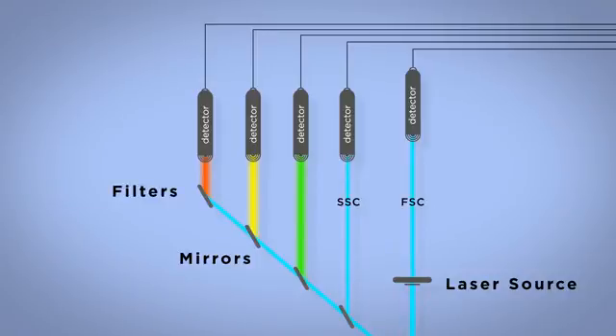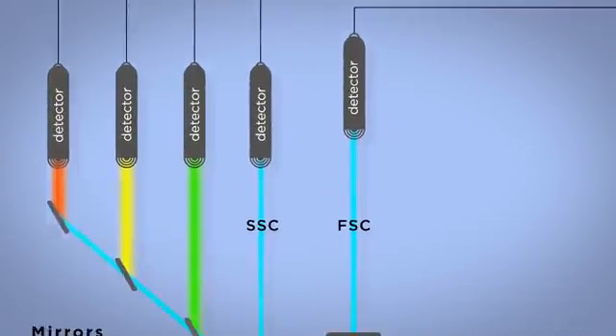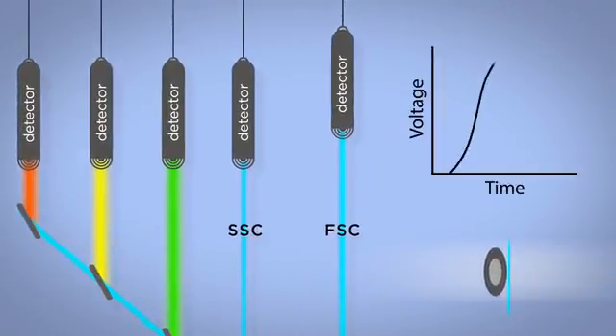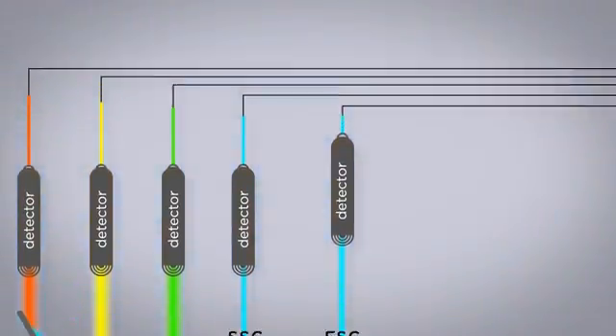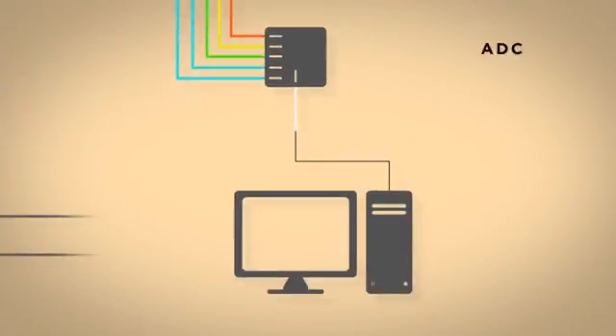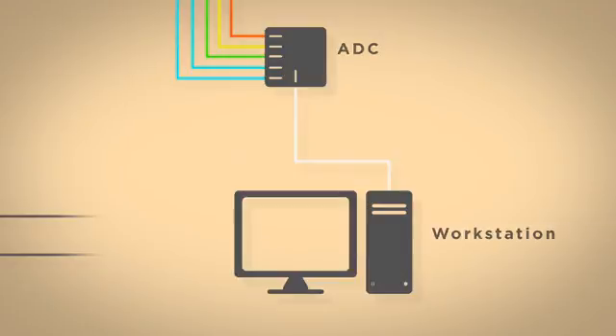The detectors convert the light energy into a voltage pulse which correlates to the intensity of that event. The electronic system then collects the pulse signals and processes them for display in the software, which can be customized to analyze the multi-parametric data.